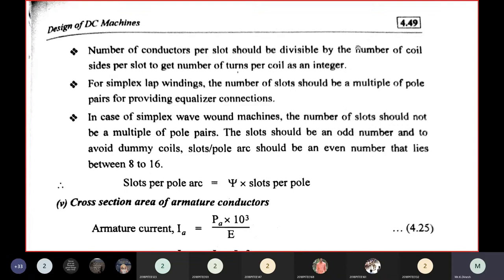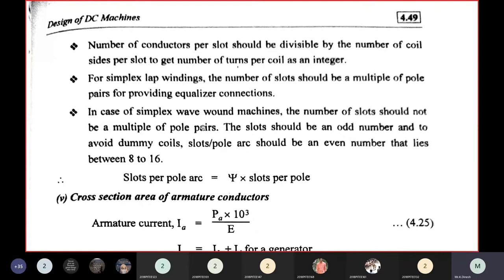For simplex lap windings, the number of slots should be a multiple of pole pairs for equalizer connections. For simplex wave-wound machines, slots should not be a multiple of pole pairs. The slot count should be an odd number, and to avoid dummy coils, slot per pole arc should be an even number between 8 to 16.